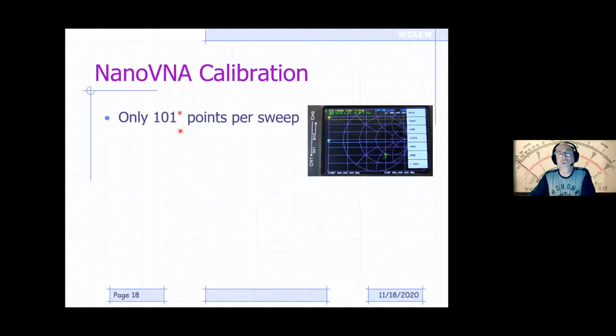The problem with that is that because it only has 101 points, you're only getting calibration specifically at those points. So if I did a 400 megahertz span, I'm going to have calibration points every 4 megahertz. Well, that'll skip right over some ham bands. They're not 4 megahertz wide, right? A lot of the VNAs will interpolate the calibration between the points, but that's not going to be as good as actually having calibration data at your points of interest. So setting up the frequency range of interest and then getting essentially 101 measurement points over that frequency range is a much, much better way to go.